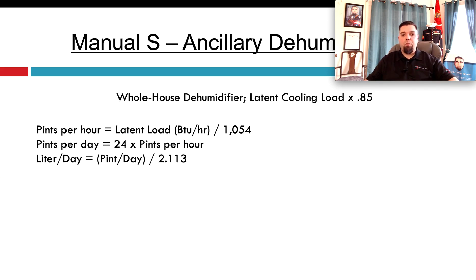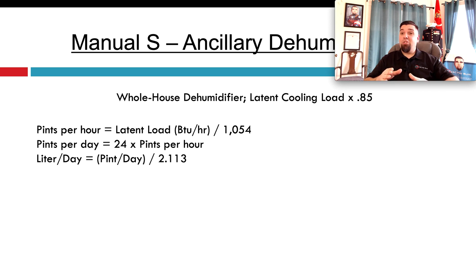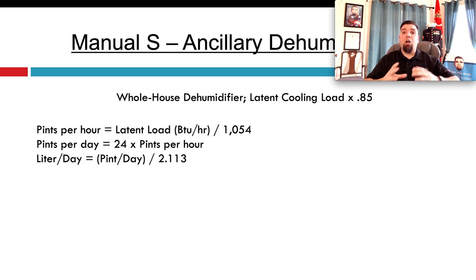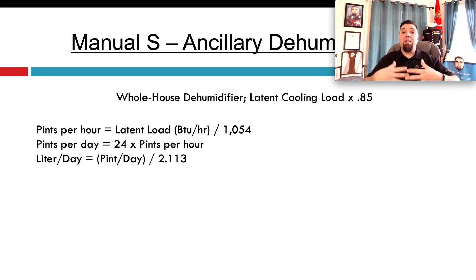Now let's talk about dehumidifiers. This is some simple math that a lot of people don't realize when you talk about a whole-house dehumidifier — this is ancillary dehumidification. It works in combination with your air conditioner. You should always meet 85% of the total latent cooling load from your load calculation.